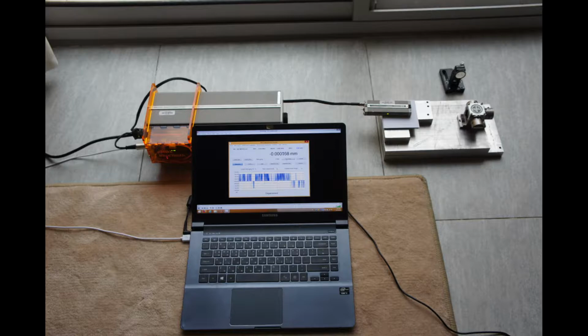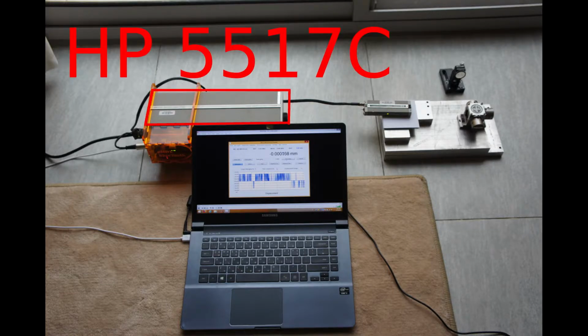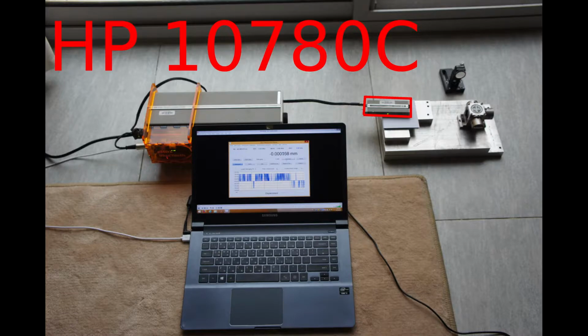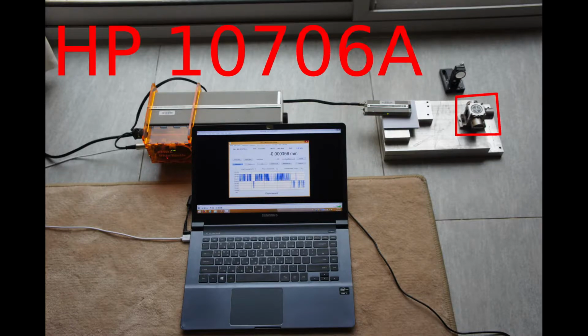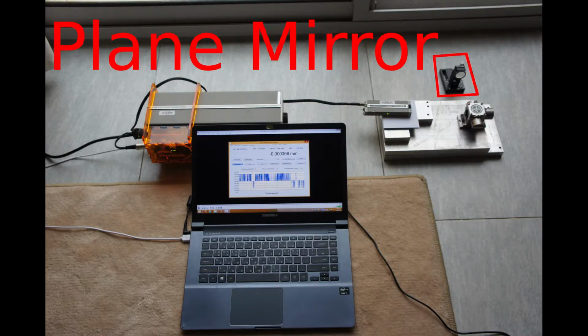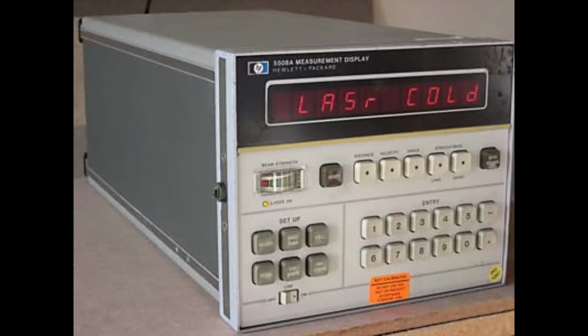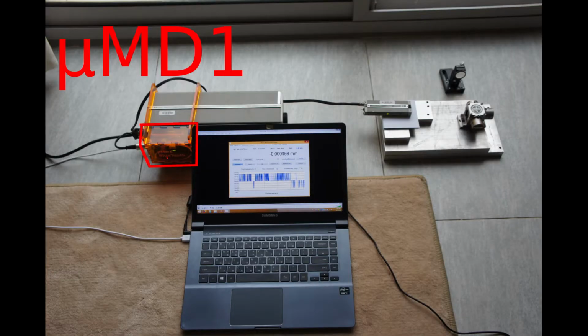Here you can see the laser, the optical receiver, the plane mirror interferometer, and the simple plane mirror. Usually the system comes with a measurement display like this, but this measurement display is very difficult to find, expensive, bulky, and it doesn't have a USB or Bluetooth interface. So instead, I'm using a µMD1 that connects via a USB cable to a computer.